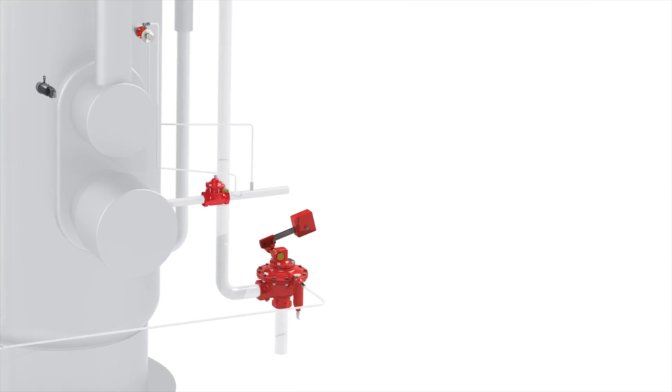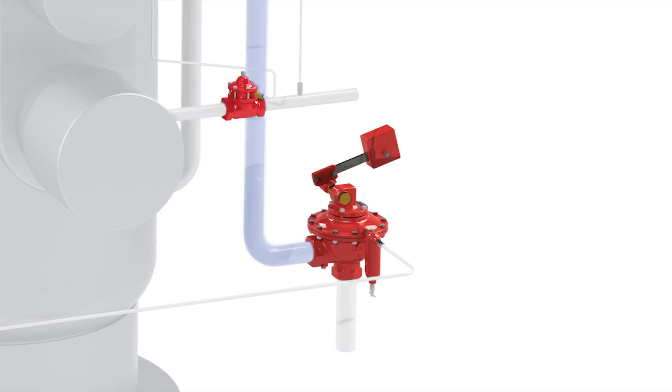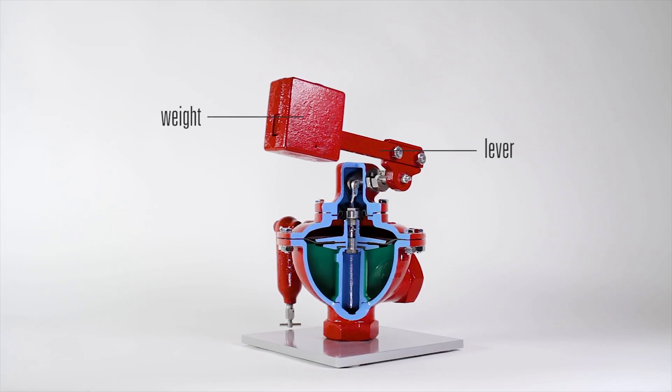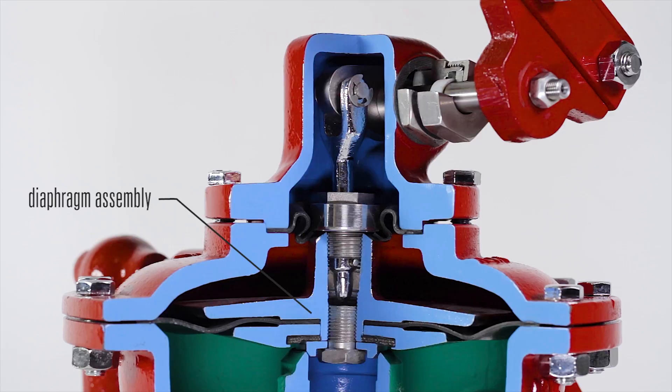The valve actuates based on the hydrostatic pressure generated from a column of liquid in the discharge piping from a vessel. The force to hold the seat closed is applied by a weight and lever which pushes down on the diaphragm assembly.